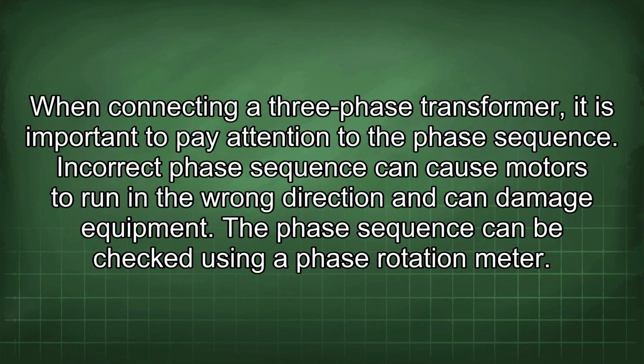When connecting a three-phase transformer, it is important to pay attention to the phase sequence. Incorrect phase sequence can cause motors to run in the wrong direction and can damage equipment. The phase sequence can be checked using a phase rotation meter.